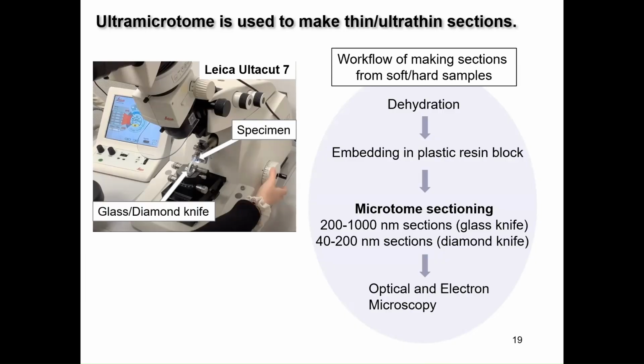So samples have to be dry, with no water, before embedding in the plastic resin. For microtome sectioning, if we are making sections for optical microscopes, we use a glass knife. We can get 200 to 1000 nanometer thickness sections. If we are sectioning for TEM, we use a diamond knife, and we can make 40 to 200 nanometer thickness sections. So depending on the section thickness, they can go to the optical microscope or the transmission electron microscope.